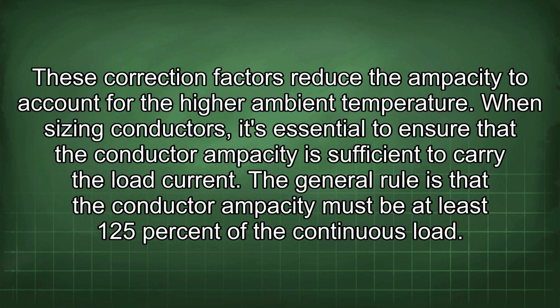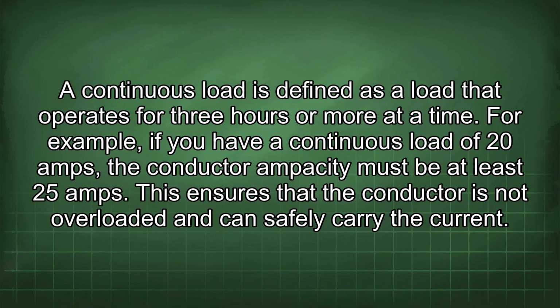When sizing conductors, it's essential to ensure that the conductor ampacity is sufficient to carry the load current. The general rule is that the conductor ampacity must be at least 125% of the continuous load. A continuous load is defined as a load that operates for 3 hours or more at a time. For example, if you have a continuous load of 20 amps, the conductor ampacity must be at least 25 amps. This ensures that the conductor is not overloaded and can safely carry the current.